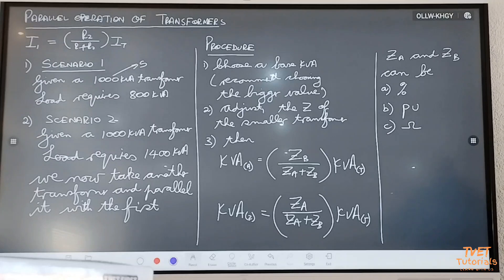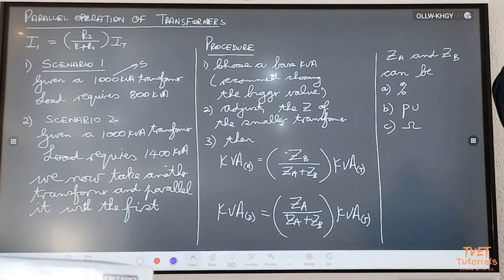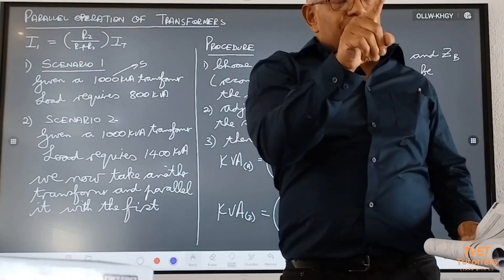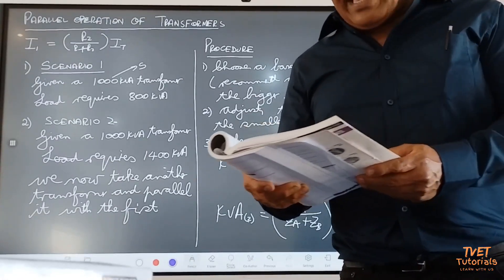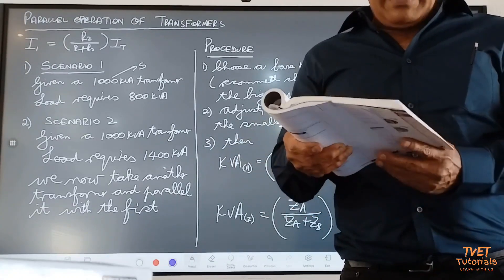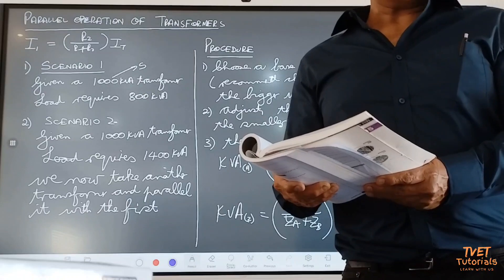If you choose the smaller value, it's just that I don't like working with fractions — but it doesn't matter at all. You can even choose a different value. The disadvantage of choosing a different value is that you have to adjust both transformer A's and transformer B's impedance — you're wasting time. But you can choose any one. The formula is: new Z equals original Z multiplied by base kVA divided by the kVA of the transformer.